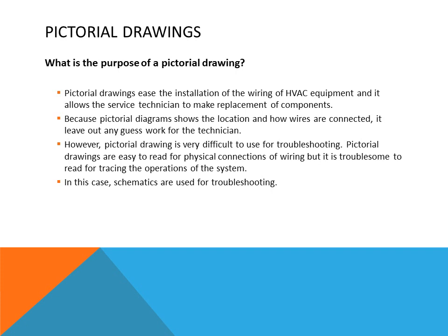So what is the purpose of a pictorial drawing? Pictorial drawings ease the installation of wiring of HVAC equipment, and allow the service technician to make replacement of components. Because a pictorial diagram shows the location and how wires are connected, it leaves out any guesswork for the technician. However, pictorial is very difficult to use for troubleshooting and should never be used for that purpose. Pictorial drawings are easy to read for physical connection of wiring, but troublesome to read for tracing the operation of the system. In this case, schematics are used for troubleshooting.